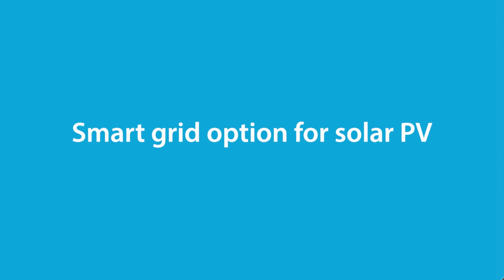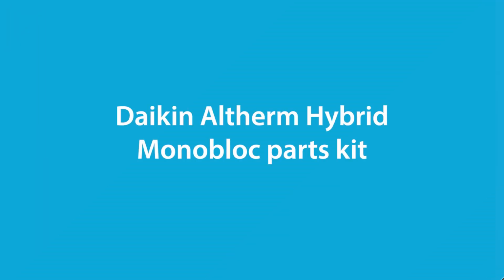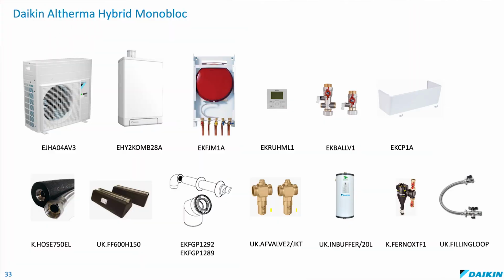The Daikin Altherma hybrid monobloc is also smart grid compatible, with the connections available on the optional adapter. This means the system can be connected to the PV panels and is then set so that the heat pump system makes use of solar grid power to heat the space and domestic hot water if connected to a storage tank. Daikin have put together complete kits of items ready to order everything you need from us to install our Daikin Altherma hybrid monobloc system.